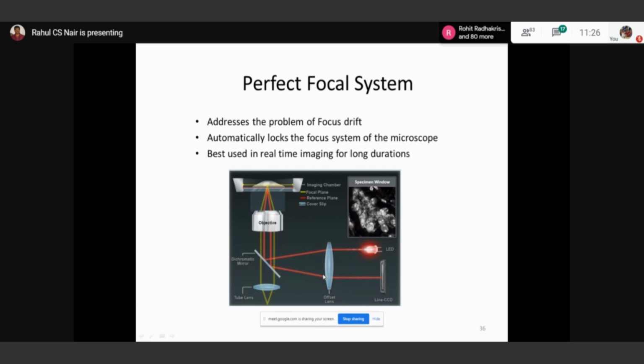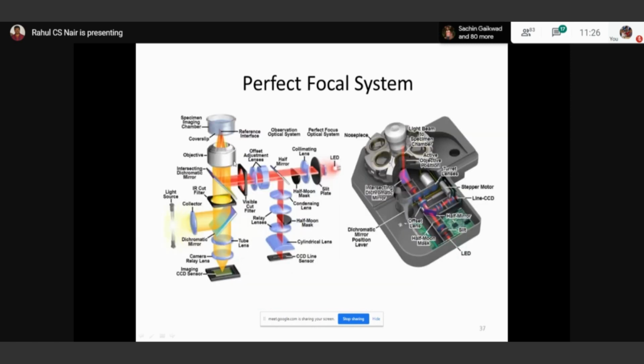This mechanism measures the correct distance here. So there are motorized mechanical parts that can adjust the objective, even if a drift occurs, and this closed loop system will work in such a way that the entire mechanism will come into perfect focus. So that is a perfect focus system. If you have a more detailed image of this, this is the perfect focus system assembly here. So you can see this red light, right? This red light is the light used for focusing alone, and it is not mingling with the imaging light. So that is the difference. The light sources are differently placed. This is the LED for this, and this is the light source for imaging. So that is the perfect focus system.